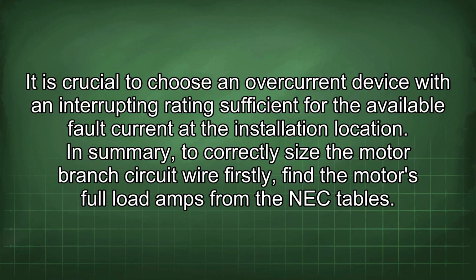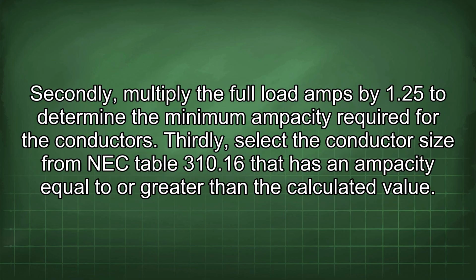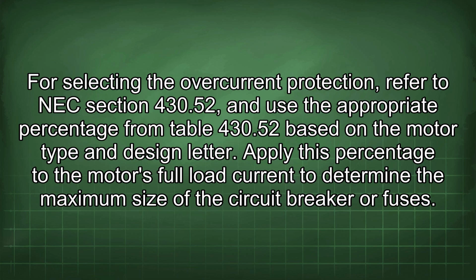In summary, to correctly size the motor branch circuit wire, firstly, find the motor's full load amps from the NEC tables. Secondly, multiply the full load amps by 1.25 to determine the minimum ampacity required for the conductors. Thirdly, select the conductor size from NEC Table 310.16 that has an ampacity equal to or greater than the calculated value. For selecting the overcurrent protection, refer to NEC section 430.52 and use the appropriate percentage from Table 430.52 based on the motor type and design letter. Apply this percentage to the motor's full load current to determine the maximum size of the circuit breaker or fuses.